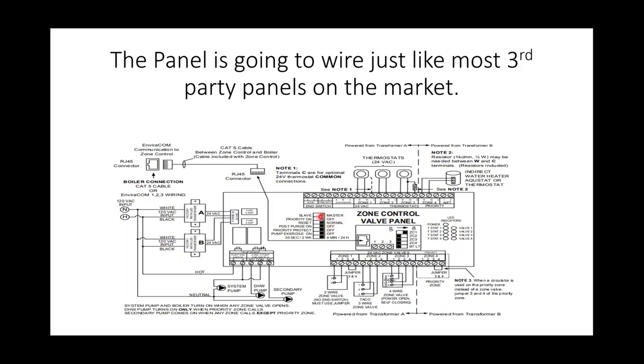If you were doing master slave, you would set the dip switches. If you're doing multiple panels, we can do up to 4 panels for a total of 16 zones. And they're going to wire the same. This one's showing wiring with zone valves and controlling the pumps off of it.